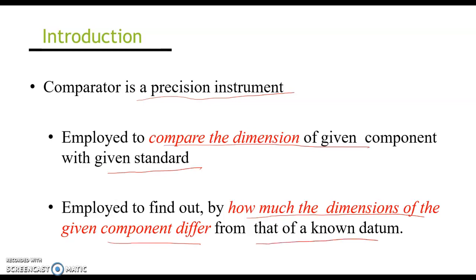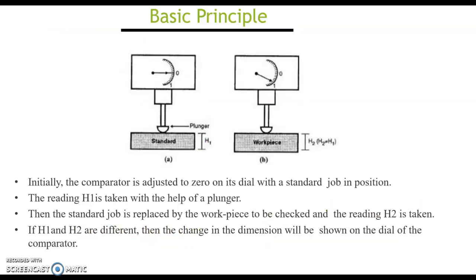The basic principle of comparators is shown in these pictures. In the first picture, the comparator is set using a standard workpiece or a gauge block — a known dimension is provided and the zero of the comparator is set using that dimension. Then, instead of the standard piece, it is replaced with the workpiece and the deflection is noted.